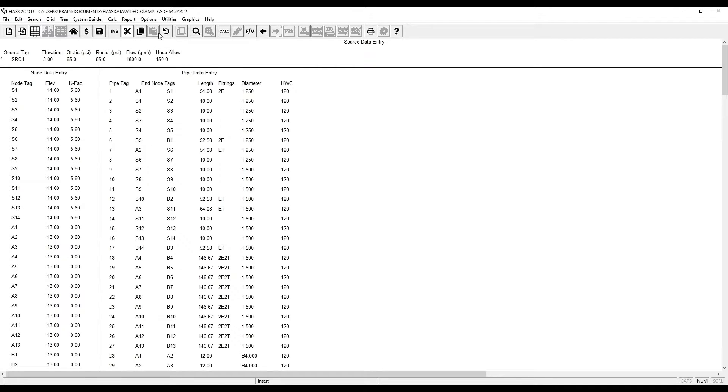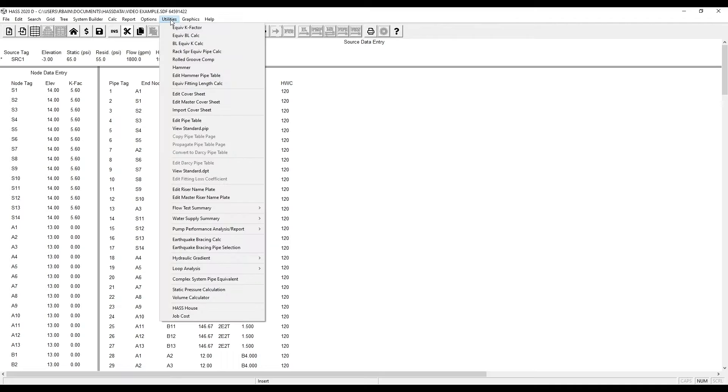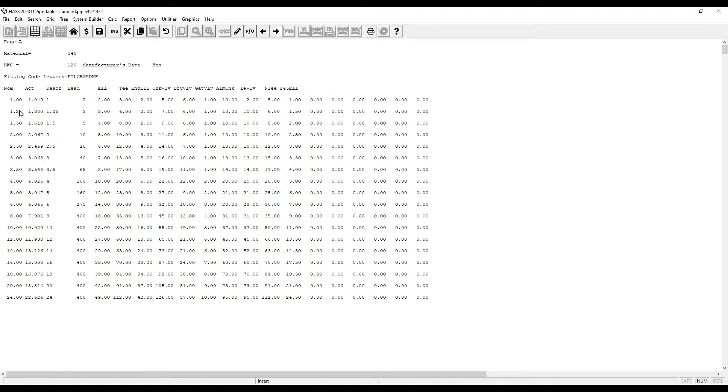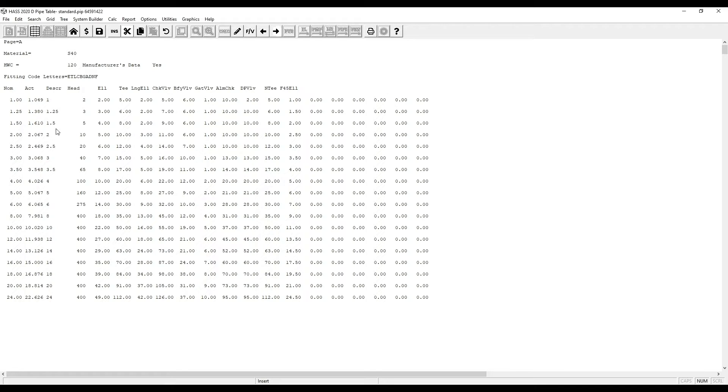If you want to see what is in page A schedule 40, go to utilities, view standard pipes. As you can see, page A material of schedule 40 with a C-factor of 120. The first column shows the nominal pipe size, second column actual, third column the description that's entered into your calculation, fourth column shows how many sprinklers would be on a pipe schedule system, then you have your fittings.